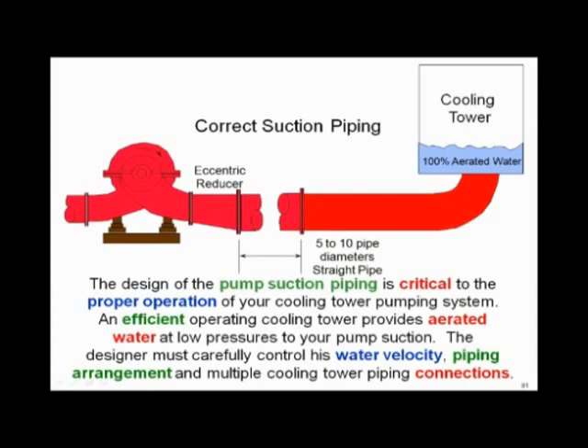So suction pipe on the tower, you want eccentric fittings on the top of the pipe, flat on top. You want your reducers on the bottom. You want to keep it as straight as you can and we want straight pipe running into it. Velocity is down. And a rule of thumb we give everybody is to keep the pressure drop between the tower and the suction flange to five feet. You can do what you want to, but it's kind of a rule of thumb. But remember, any pressure drop on that water, you're going to get air out. That's the thing you need to remember.